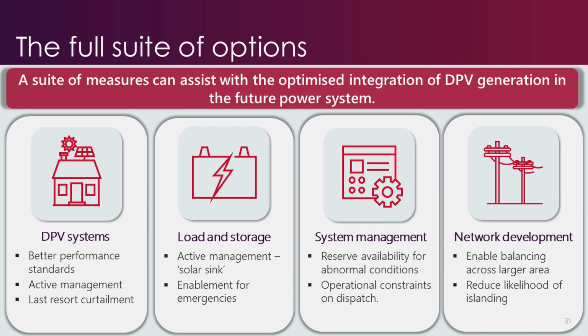The system is designed to be able to cope with a range of operating conditions. These range from normal day-to-day operation, abnormal conditions associated with the sudden disconnection of a large generator or a major transmission path, and also extreme abnormal conditions associated with exceedingly rare events, such as regions islanding from the NEM or at elevated risk of doing so, and system recovery and restoration following major system events. We've classified measures across 4 categories below. First, on the left, measures directly touching the DPV systems themselves. Our key recommendations are in this category, so I'll come back to this shortly.